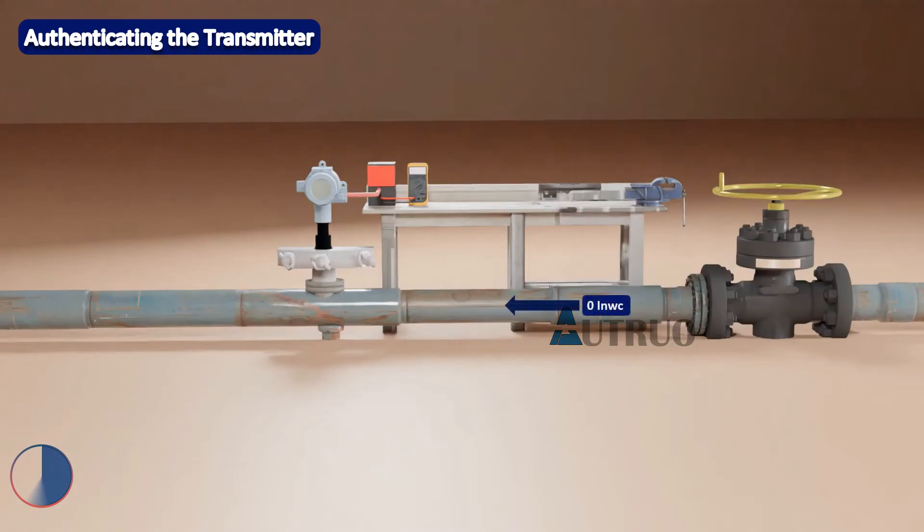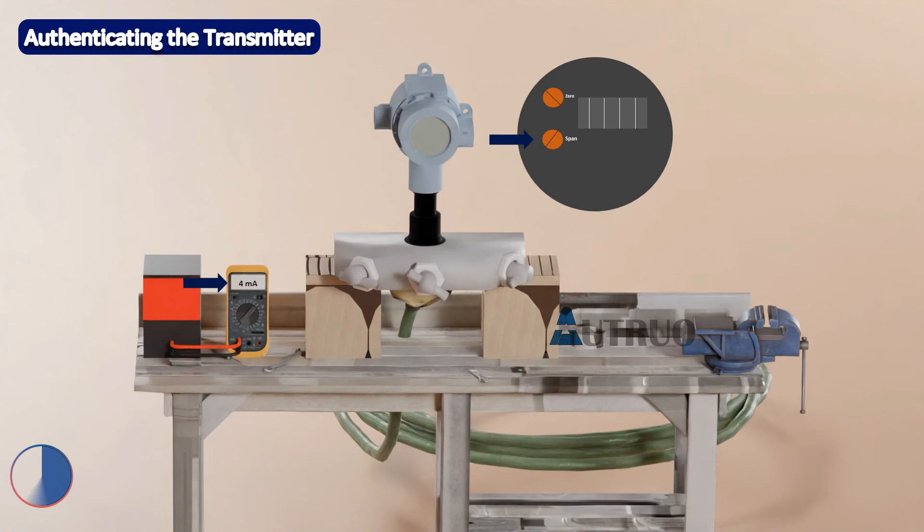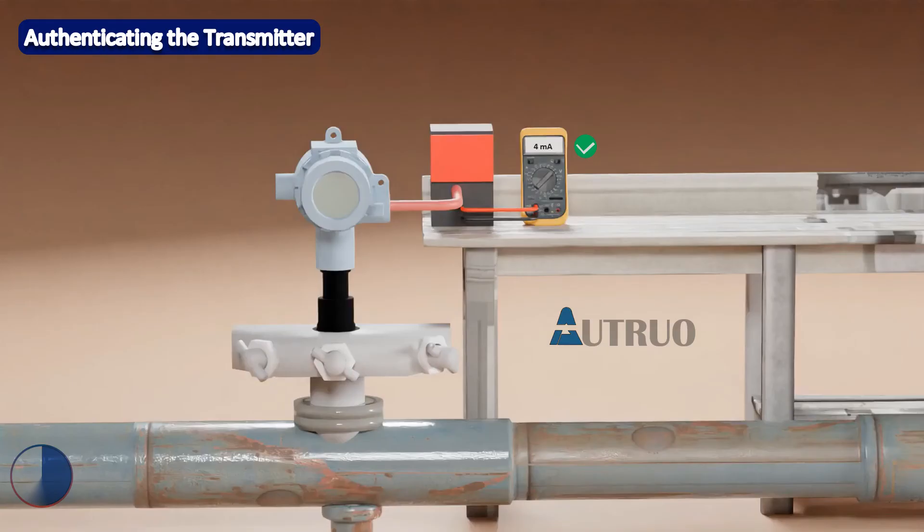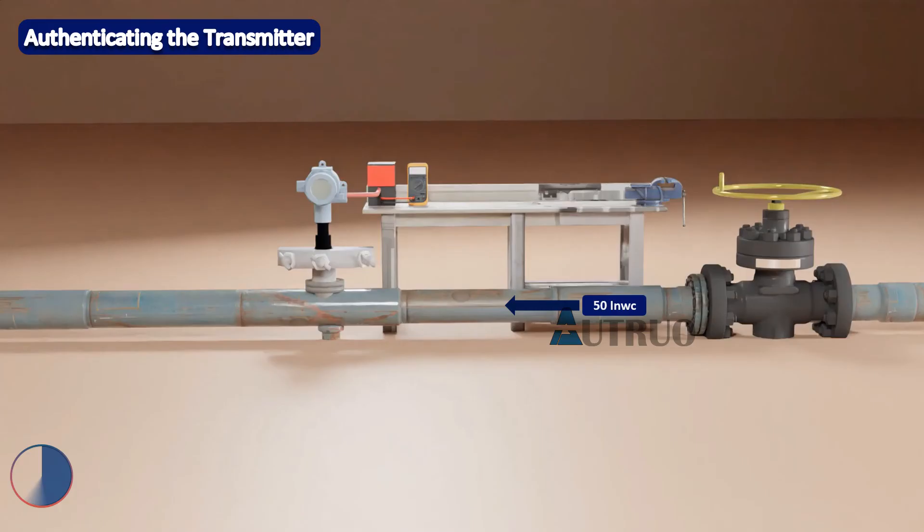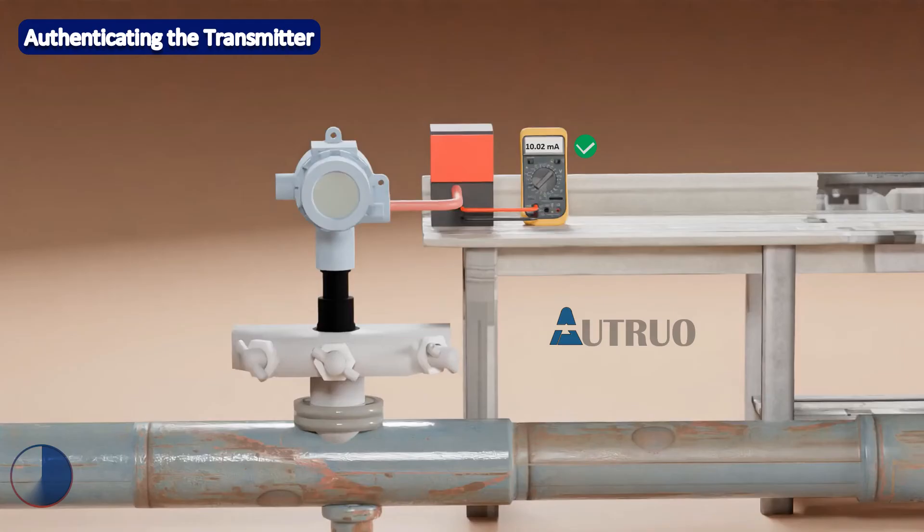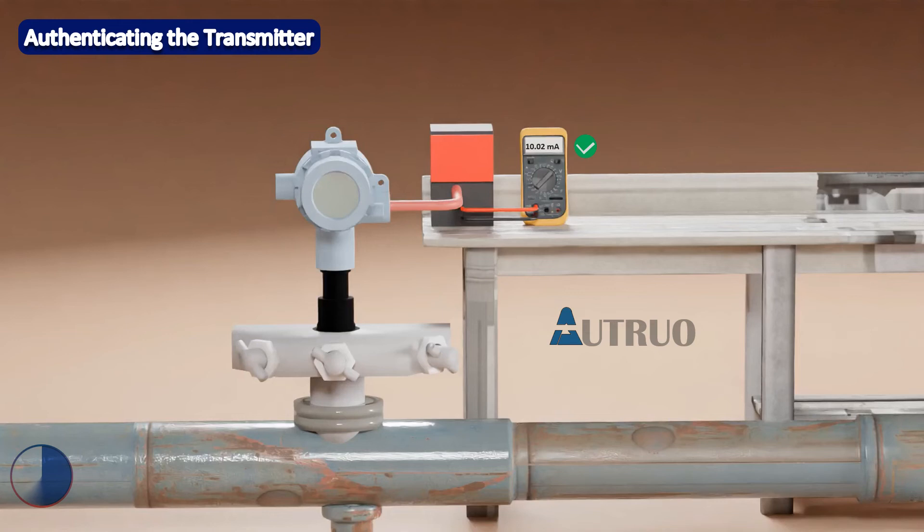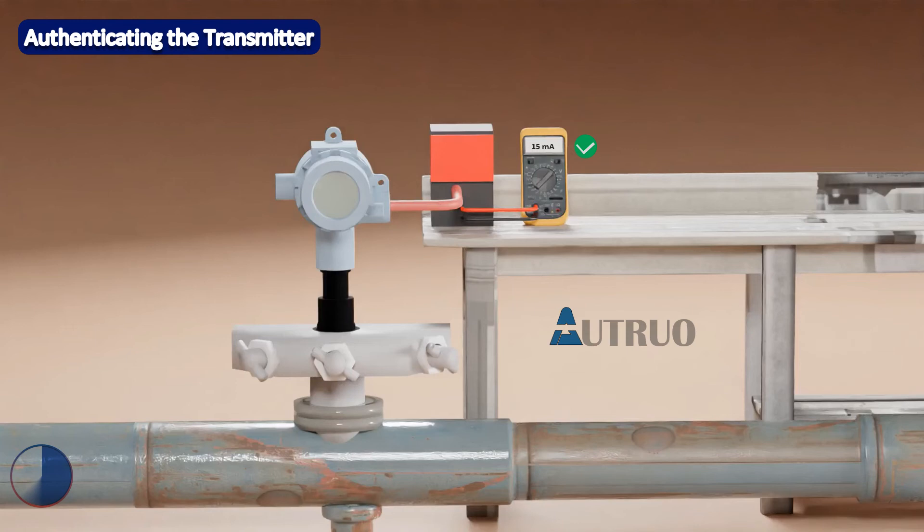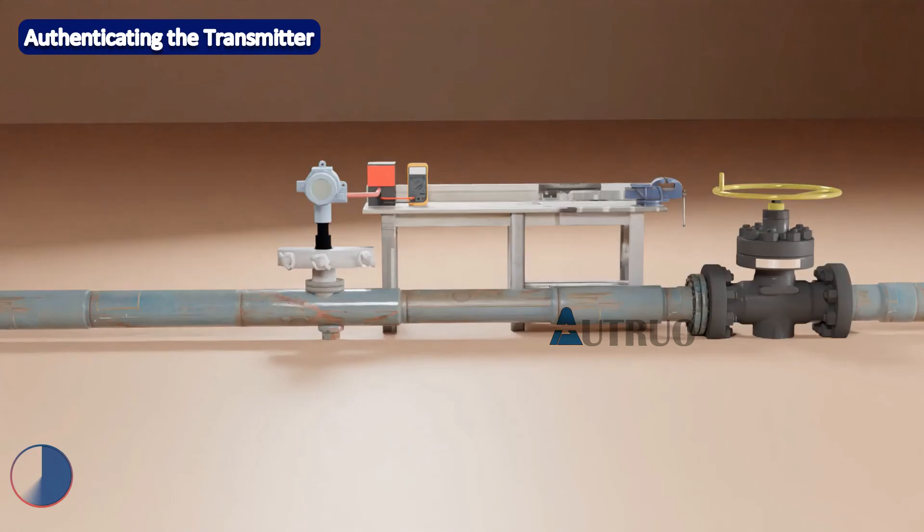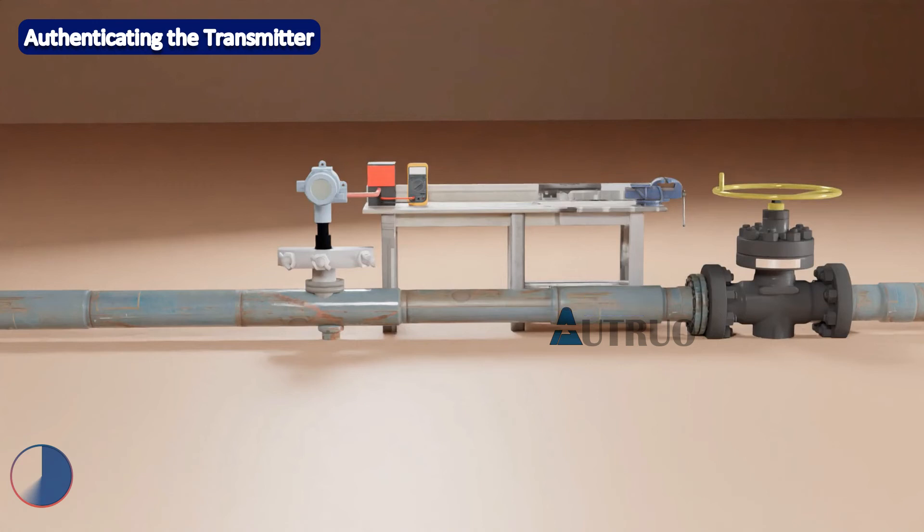Now when there is no liquid flow, the current gotten is 4 milliampere. When the valve is open halfway, which is to allow 50 inch of water column to flow, the current gotten is 10.02 milliampere. Again, when the valve is further opened slightly, that is when 75 inch of water column is allowed to flow within the pipe, the current gotten is 15 milliampere. Finally when the water inlet valve is open to its maximum, that is to allow 100 inch of water column to flow within the pipe, the current gotten is 20 milliampere.